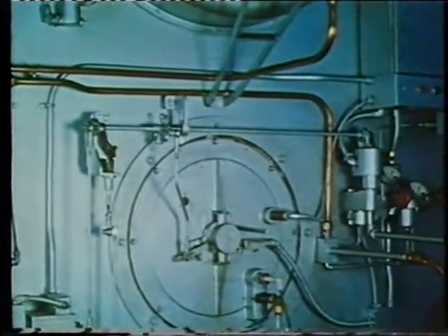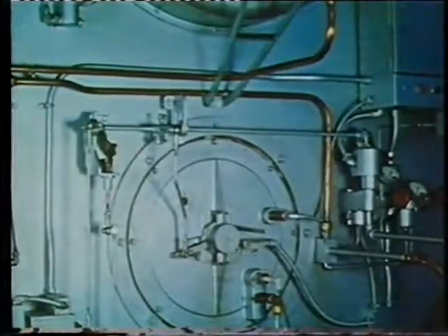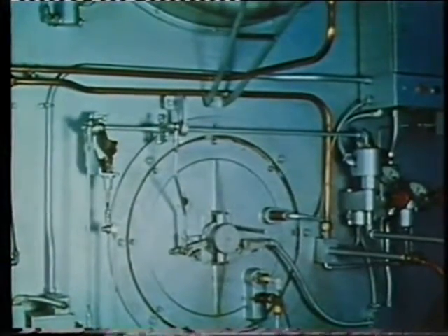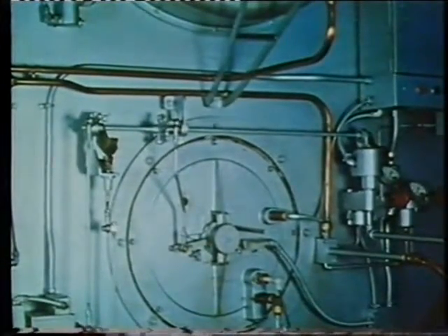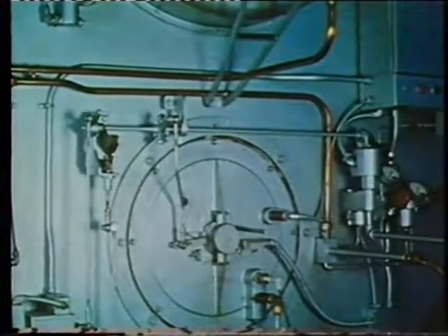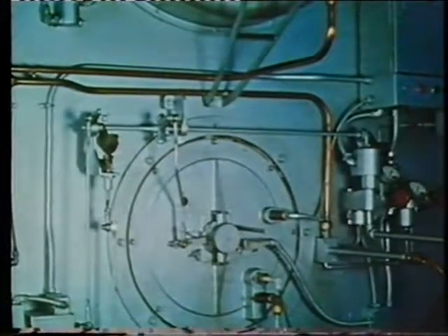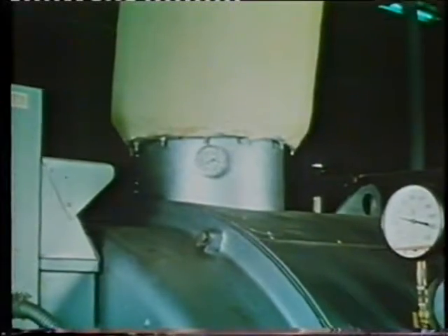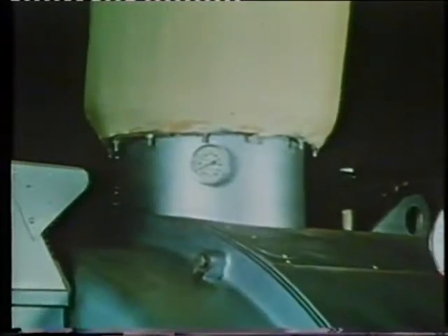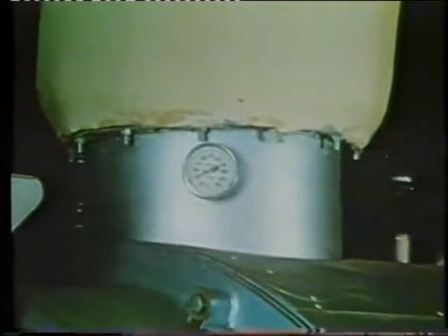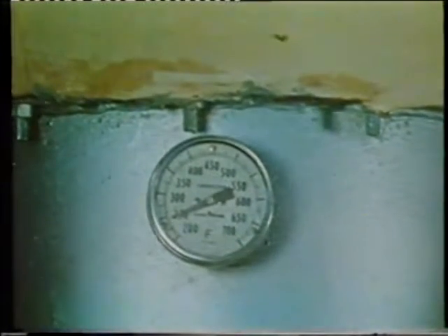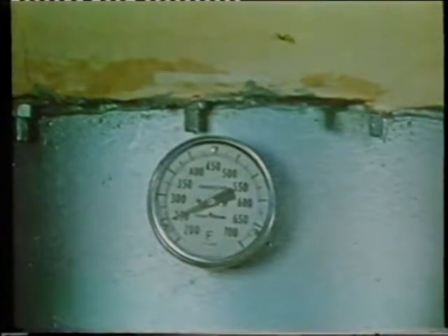When the linkages are properly adjusted, a coordinated movement of the damper and metering cams within the limits of the modulating motor travel will provide the proper fuel-air ratios through the firing range to meet the load demands on the boiler. The stack temperature thermometer tells the fireman if he is getting full utilization of combustion gases. If the temperature is higher than normal, flue gases are not giving up heat to the water, perhaps because of dirty boiler tubes.